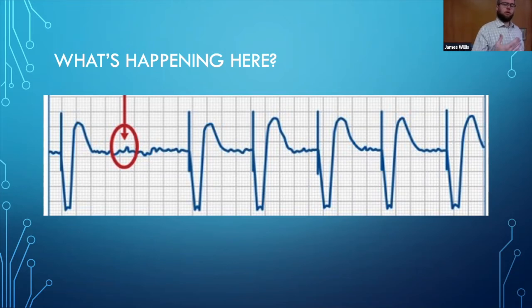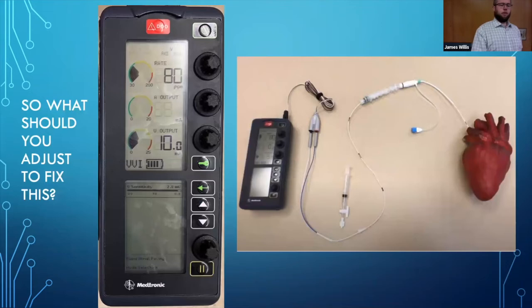So we know that there's an output failure. We know that there's something going wrong with the pacemaker. So what do you want to do to troubleshoot this? Whether we're not getting enough energy or not getting the wires. Let's go back to our ECG. We saw the output failure, right? We saw it there on the ECG. Next thing we're going to do is go back to the wires and the patient. Start at the patient, make sure the wire is still intact. No one cut it by accident while they were changing something.